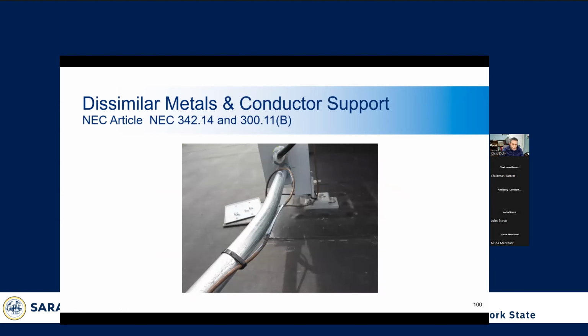Here we see a similar thing. Raceways are not really approved to have electrical wire carried on the outside of the conduit. Pretty much the only thing you can have running on the outside of a conduit is like data wire. So you can see they ran the ground conductor all along the outside of this conduit, and wherever it's touching, it's corroding. That's because again they're dissimilar metals and they corrode when they're in contact. So over time, that's going to just corrode all the way, and then you'll have a disconnected ground path.